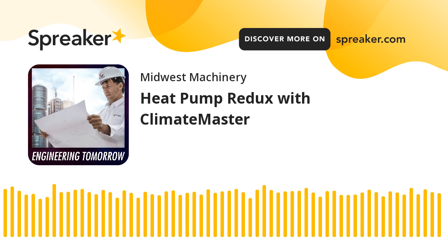So up on the screen, real simple, we have a summer operation. All the zones in the building typically will require cooling. So what happens when our heat pump is in the cooling mode, it's dumping warmer water back into the system loop. And again, our operational range for a closed loop traditional water source heat pump is 60 degrees to 90 degrees. So as we're dumping warmer water and all these units in the building are operating in cooling mode, every unit is dumping warmer water back into that loop, raising the temp.